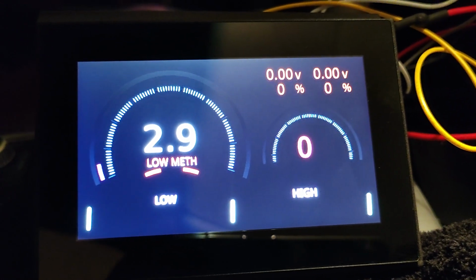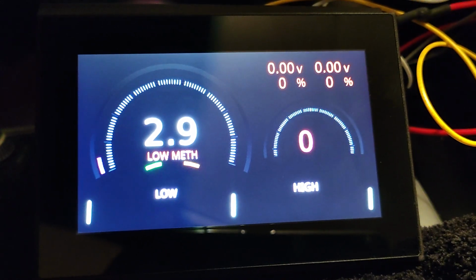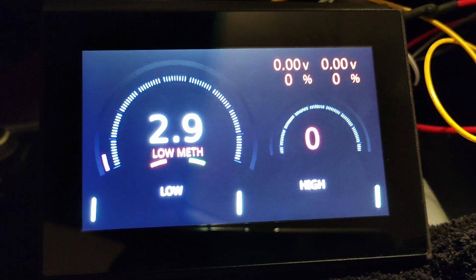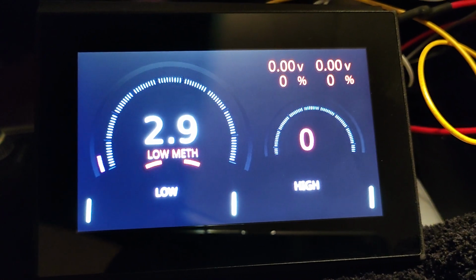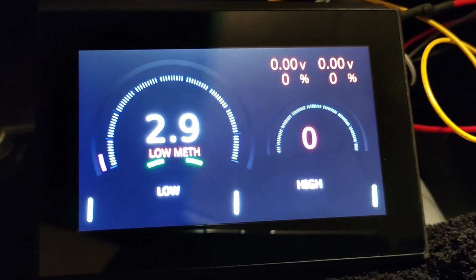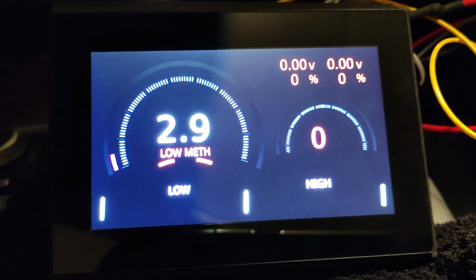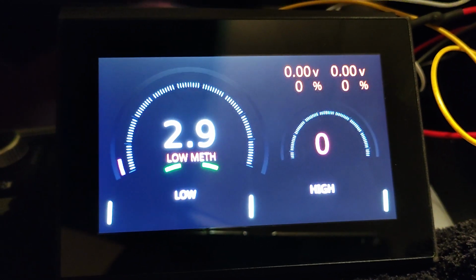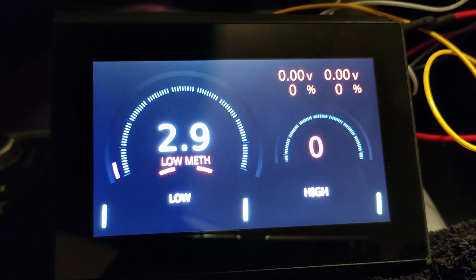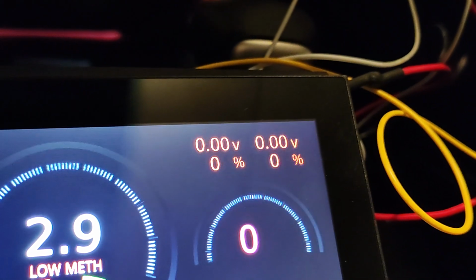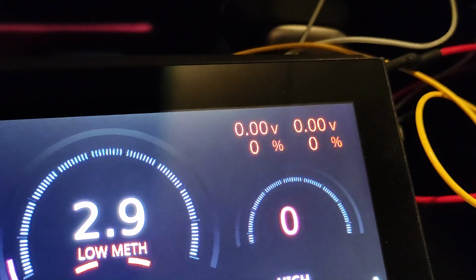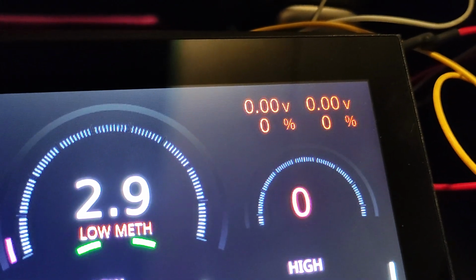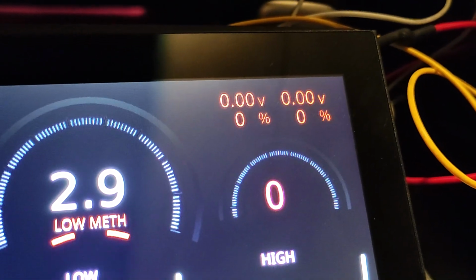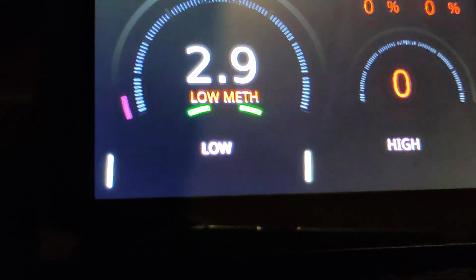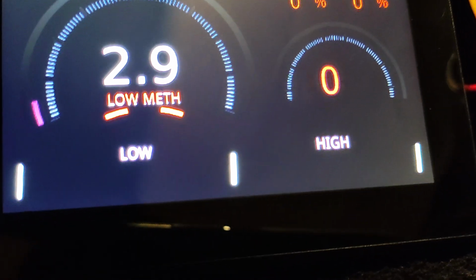So if the transducer is reading less than 0.492, something like that, then that means the VREF voltage for the transducers are not reading correctly, and we know we have an issue. They should read, unless there's an error, but for a little bit of margin, they'll read 0.5 volts at all times. So if for some reason they read less than 0.5 volts, those two alarms there will go off, and the letters in the top right corner will turn red. Originally, if there is no error, the left side will be green and the right side will be blue, just like before. And then the same bar scaling is down here under low and high, but right now there's no flow, so we have no bars.